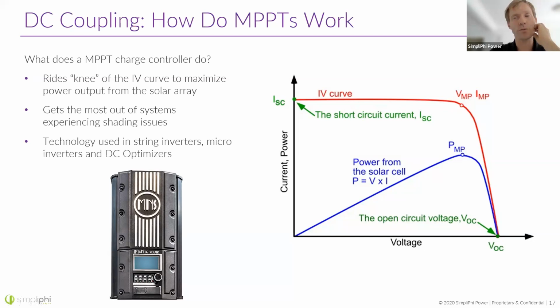Of course, that red curve changes constantly throughout the day as the panel heats up or cools down, as shading comes in, etc., based on array conditions. Your MPPT is constantly making little adjustments - drawing more current and seeing the voltage go down, then drawing less current and seeing the voltage go up. The job of the MPPT is to move around and stay at the top of this maximum power point, getting the most power possible out of the panels. What I've shown here is a Midnite Solar charge controller - as Daniel said, many of these charge controllers are just built in.